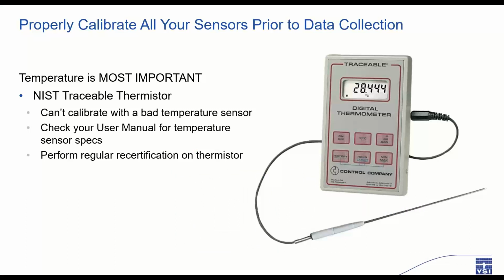The first step to the calibration process is you always must verify that your temperature sensor is giving you accurate readings. All water quality sensors depend on a working temperature sensor to provide reliable data. If the temperature sensor is bad, there's no reason to proceed with calibrations. You will need to replace it before you move on because there's no way to calibrate a temperature sensor on most devices. In order to determine if your temperature is reading accurately, grab a NIST traceable thermometer or other certified thermometer and check it against your instrument's temperature. Make sure that the thermistor is within specification and you are good to go.